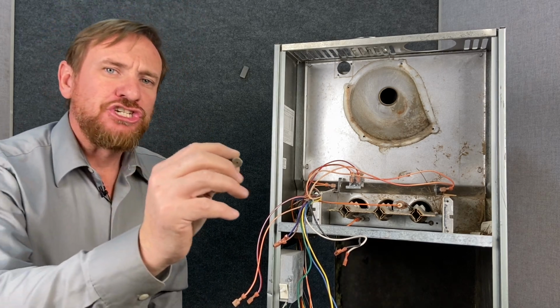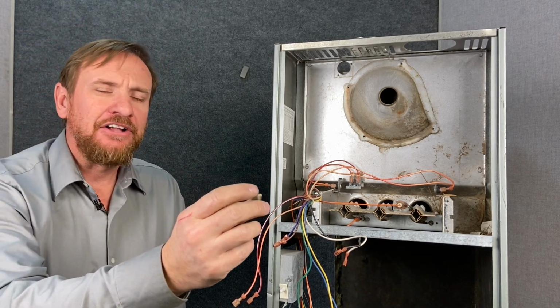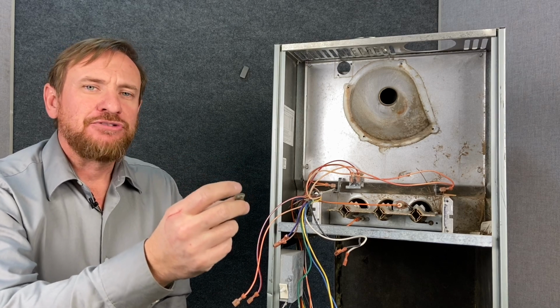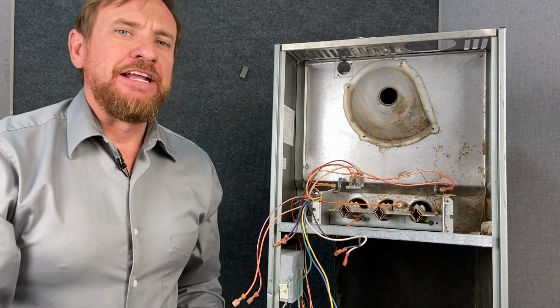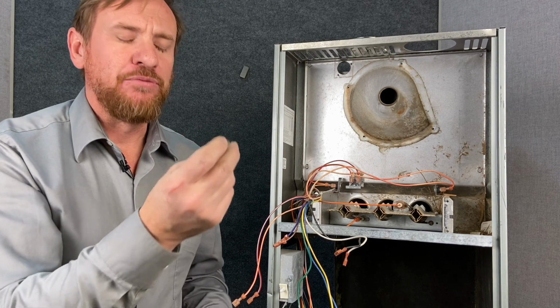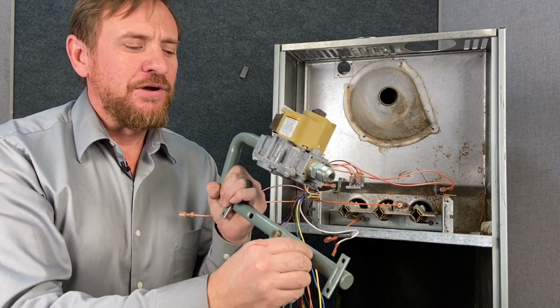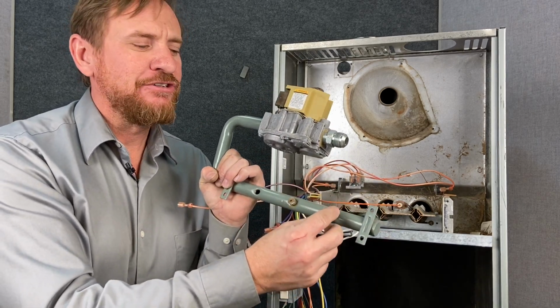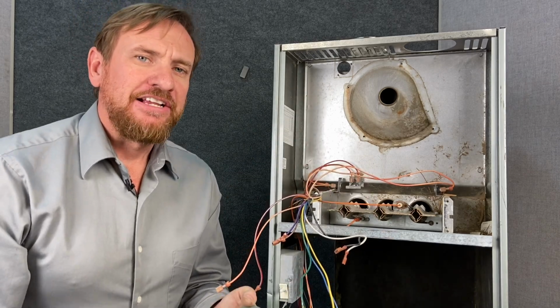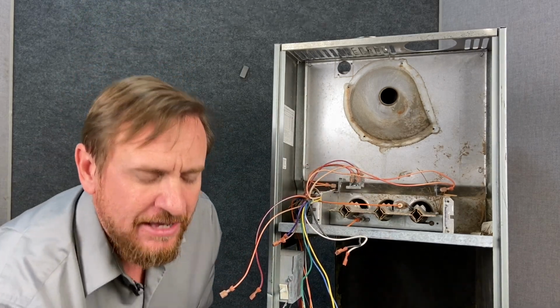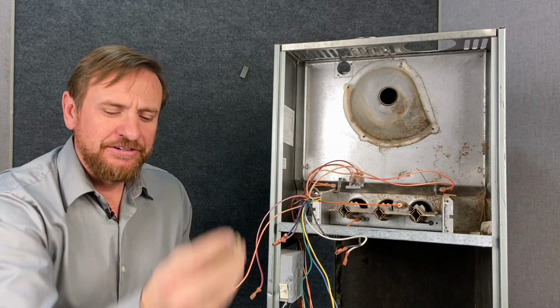So sometimes you're going to have to change these orifices out, especially if you're at altitude or you're converting it from natural gas to propane. You have to follow the manufacturer's instructions on what size and when to do that. So just because it came with an orifice size doesn't mean that that's the size you're going to be using, especially when you get into combustion analysis. Follow the manufacturer's instructions, but that is a spud and the hole in the center is an orifice.